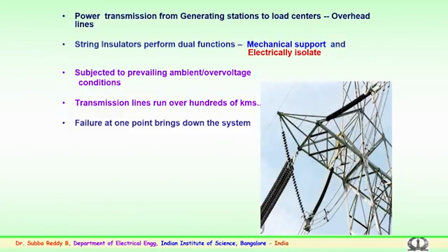So, over voltages, we will be seeing, may be because of the normal power frequency working voltages. The over voltages may be because of lightning, known as lightning surges or lightning impulses, which are seen on the transmission system, then switching surges or switching impulses, which are seen because of the opening and closing of the circuit breakers. So, the insulators will be subjected to this type of conditions, and they have to withstand them in the field.